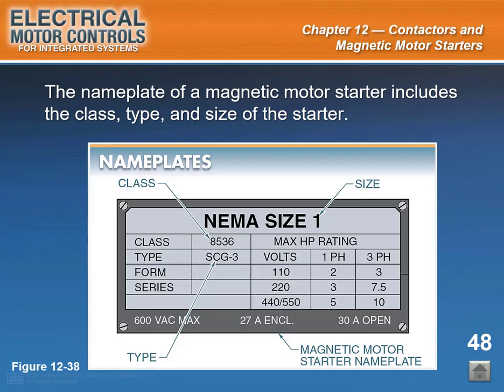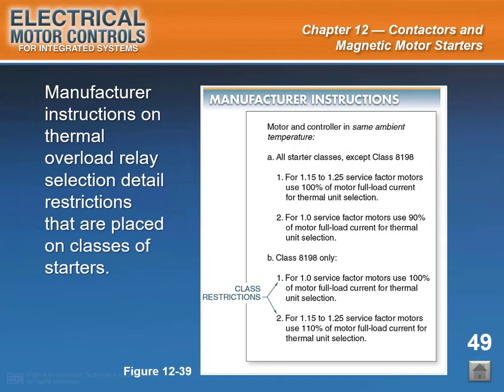The class, type, and size information of a magnetic motor starter are found on the nameplate on the face of the starter. The phase, service factor, and full load current of the motor are determined from the motor nameplate. Common applications use 40 degrees Celsius as the ambient temperature. Questionable ambient temperatures should be measured at the job site or determined by some other method. End of slide 48.